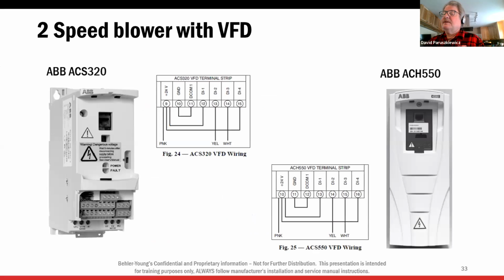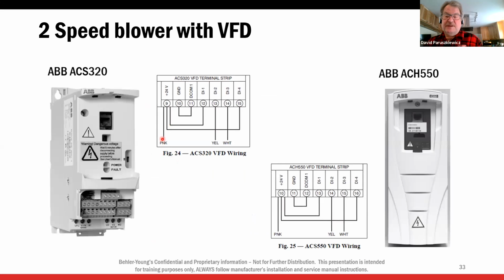24 volts. The VFD creates 24 volts DC, not AC like your transformer, but DC. So between here and here, your ground is 24 volts DC. So what does it do with the 24 volts DC? It sends it down this pink wire. Now, if you look, all the wires here, but this pink wire goes here, it jumps to terminal 15 and it jumps to terminal 12.